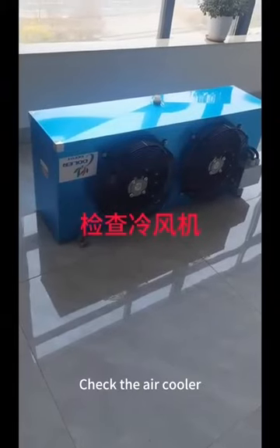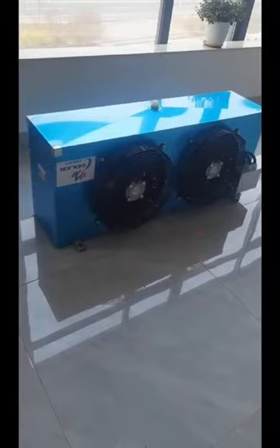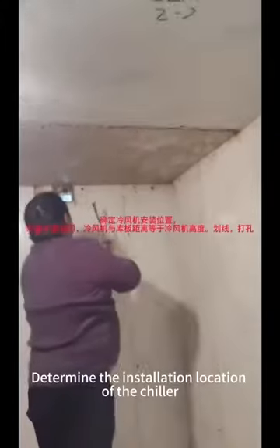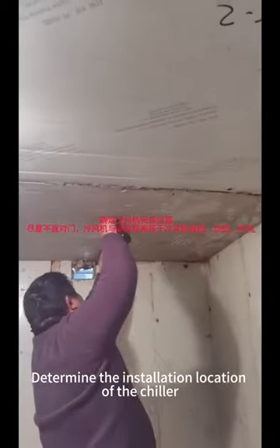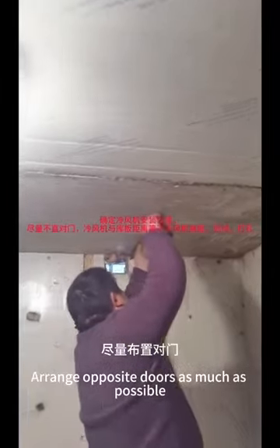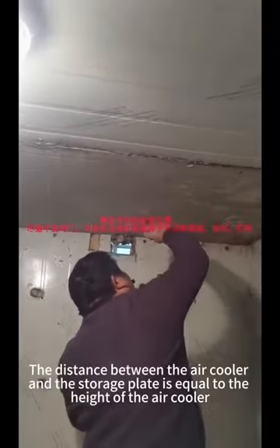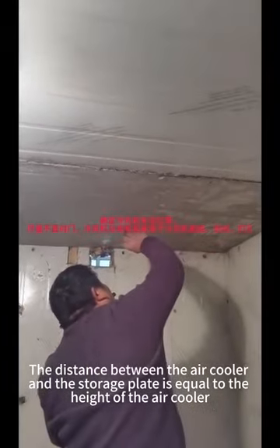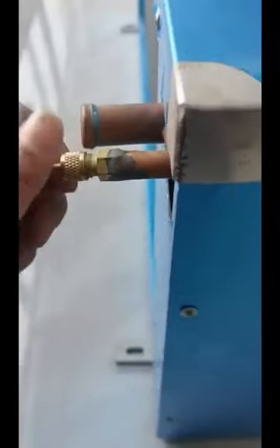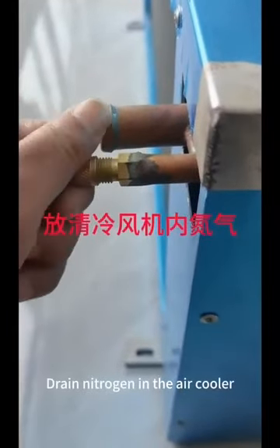Check the air cooler. Measure size. Determine the installation location of the chiller. Arrange opposite doors as much as possible. The distance between the air cooler and the storage plate is equal to the height of the air cooler. Scribe and punch. Drain nitrogen in the air cooler.